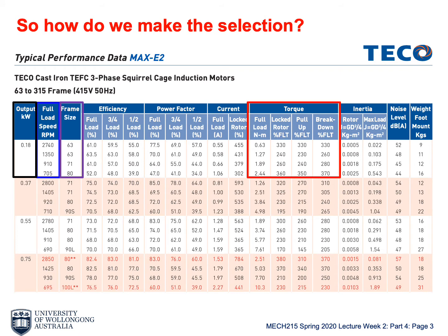It's 330%. And there's a pull-up torque, which is slightly smaller than the locked rotor torque. Then there's a breakdown torque, which is similar to or higher than the locked rotor torque. These 3 values all together combine to make up the run-up curve for the motor. So these 4 columns give us the information to choose the motor for the speed, for the size, for the torque, and for the output power.